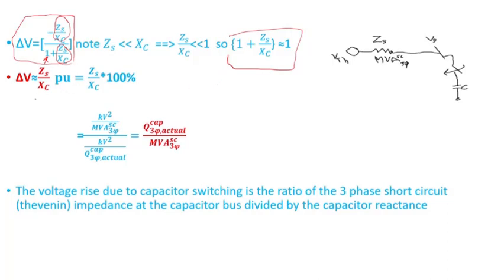We're trying to estimate delta V — the voltage difference between before closing the capacitor bank switch and after the capacitor bank is switched in. This is an estimation because we are making the assumption that ZS is much smaller than XC, so that denominator term approximates to one. Therefore, delta V equals the Thevenin impedance divided by the impedance of the capacitor bank, in per unit — multiply by 100 if you want it in percent.